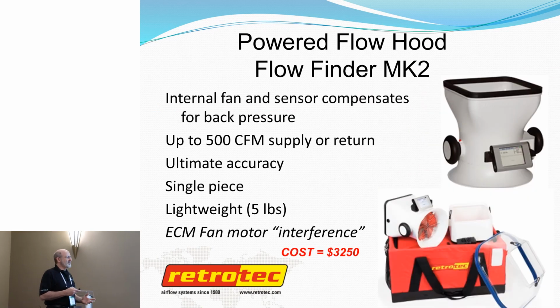Unfortunately, no longer in production, but some people have them. This powered flow hood made in Norway has a sensor in the fan to correct. It runs up to 500 CFM. We call it the ultimate in measurement. It's single piece, battery operated. You literally turn it on, seal it over the grill, press a button, and in 15 seconds, your CFM number is there along with the direction of flow.